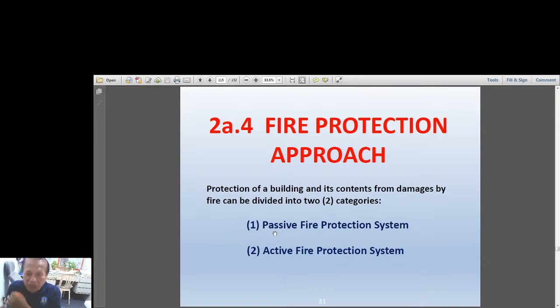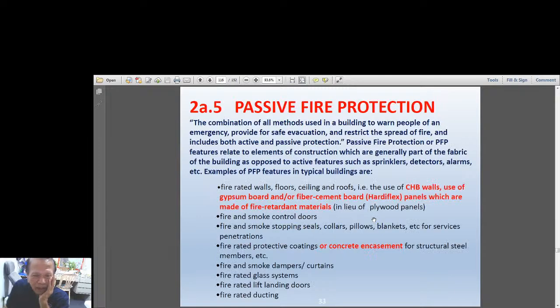Passive are the materials that are used in the building. For example, when you use concrete hollow blocks, then it is a fire retardant material. But if you use plywood, then that's not protection. Plywood would help spread the fire because it is a flammable material. And non-retardant plastic materials are also not passive fire protection. So passive fire protection is the selection of materials that have fire rating.